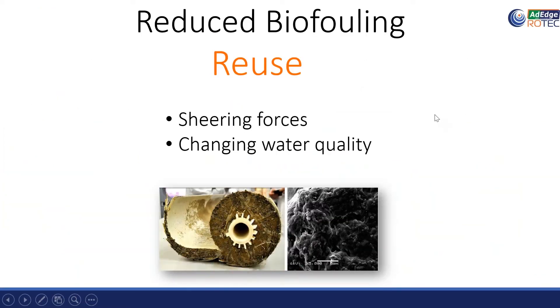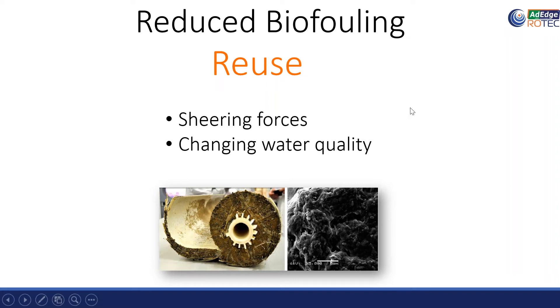We can also reduce biofouling of the membrane, which is very important for reuse applications when we use treated wastewater effluent. The reason this is happening is that when we reverse the flow, we create shearing forces that probably interfere with the buildup of biofilm. In addition, we change the water quality — the osmotic pressure changes and interferes with the proliferation of bacteria.